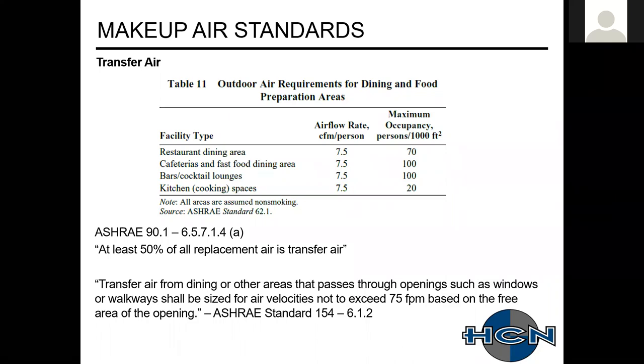ASHRAE 90.1 calls for this for anything over 5,000 CFM. Actually, ASHRAE Standard 154, I think, goes below that too. They want you to do that just because you're already heating and cooling that air, and then we're going to be exhausting it out the hood. So why not use that, and keep the cooks and staff a little bit cooler? The big thing with that is we want to make sure we limit the velocity going through there. If you only have open kitchens, this is great. That's the big thing going on in the industry. But if you have closed doors, double doors, that kind of stuff, you want to keep the velocity going through there as slow as you can.